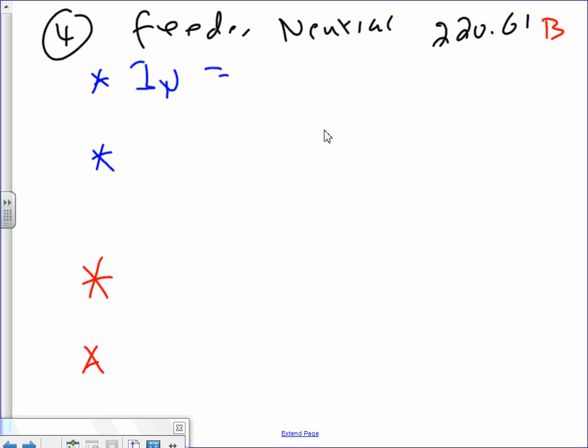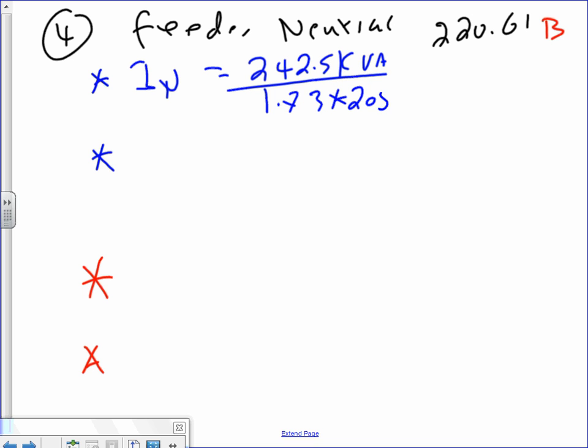Okay, last thing. Neutral. Let's do the neutral quick, guys, before our friends come here. The neutral size, guys, we have 242 kVA. 242.5 kVA divided by 1.73 times 208 equals 674. We just did that, right?